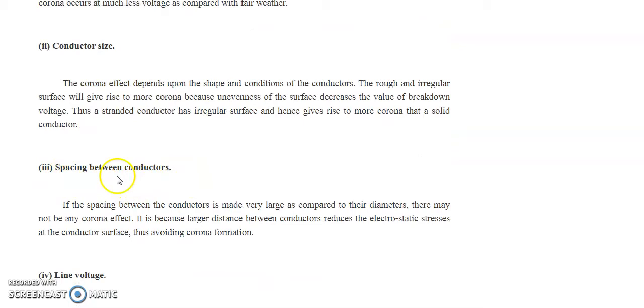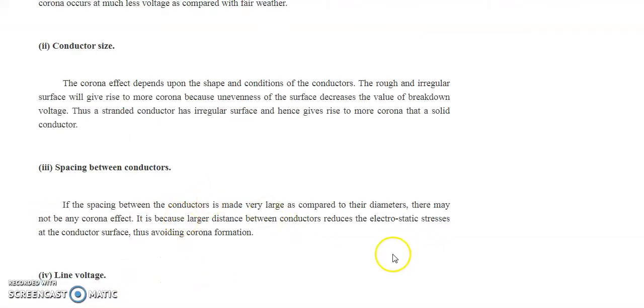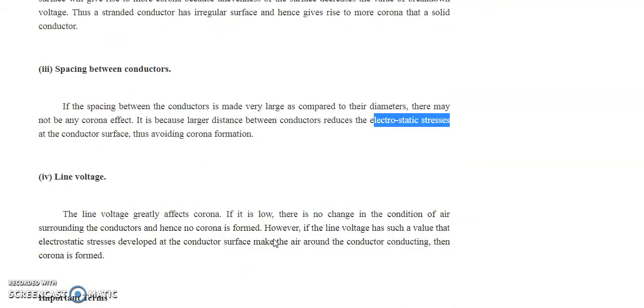And third, spacing between the conductors. If the spacing between the conductors is very large compared to the diameter of the conductor, that means the diameter of the conductor is very small. You imagine the distance between these two conductors is very large, then the corona possibility will be very less, because the electrostatic stress is very less. That is, your potential gradient is very less, and electrostatic stress is less, and that's why it will reduce the corona formation.